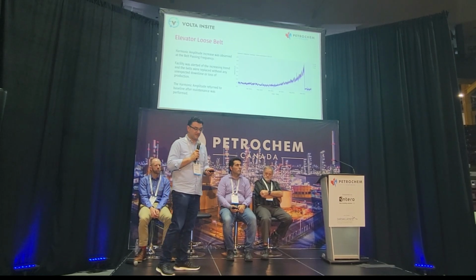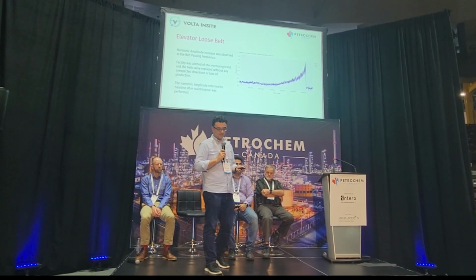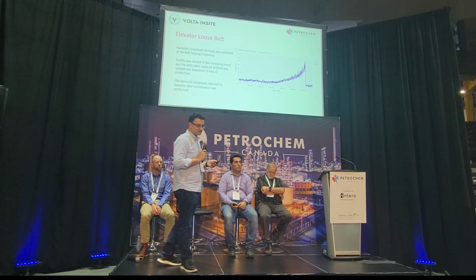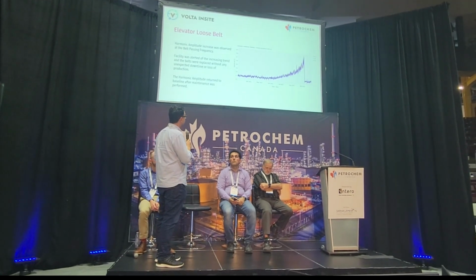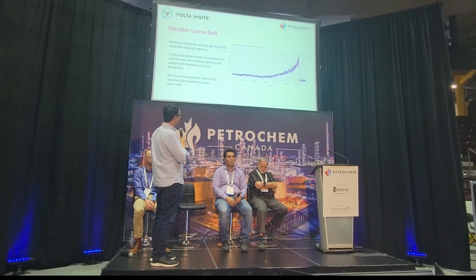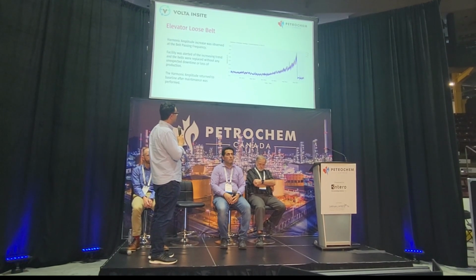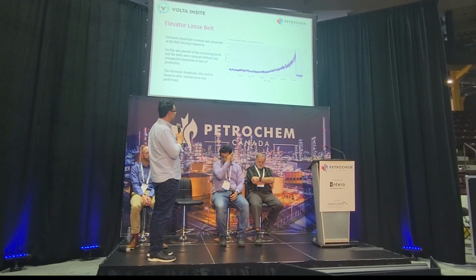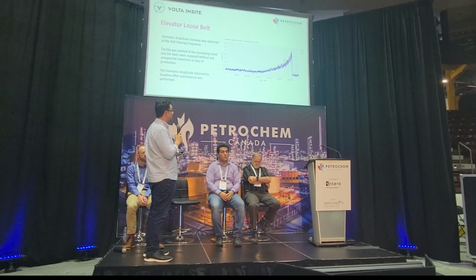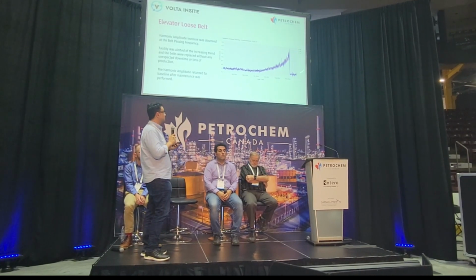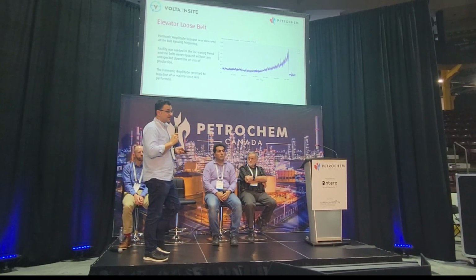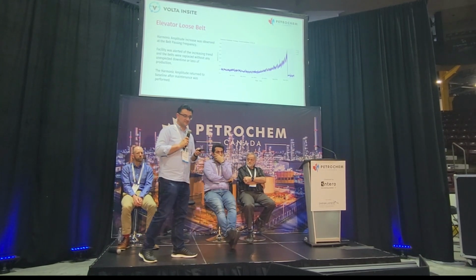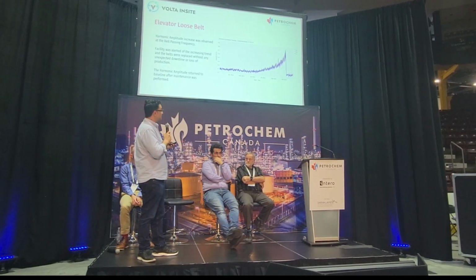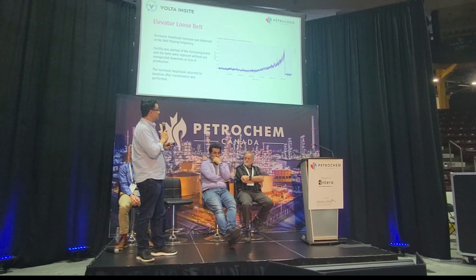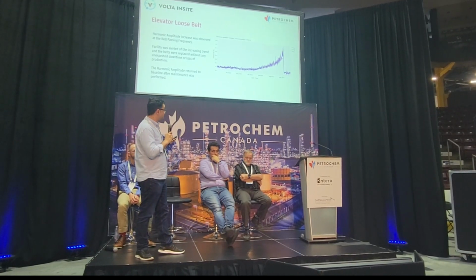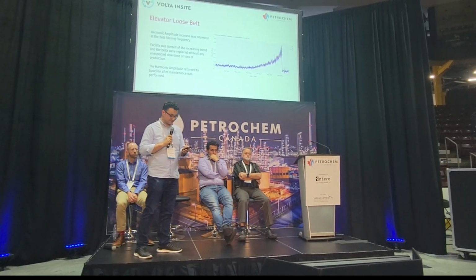So this is an example of an elevator loose belt. Specific harmonic is 0.71 of line frequency. And you'll notice back in April of 21, we had baselined the system, and over time this starts to trend upwards. We send an alert to the facility guys to go check it out. Yes, indeed, we've got a loose belt on our hands. They perform maintenance, and the harmonic comes back down to baseline.